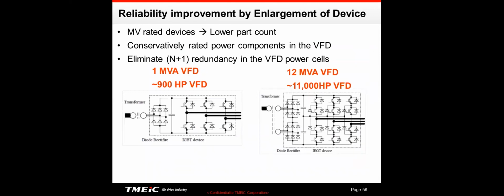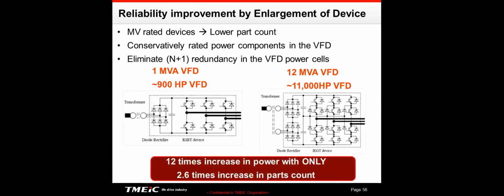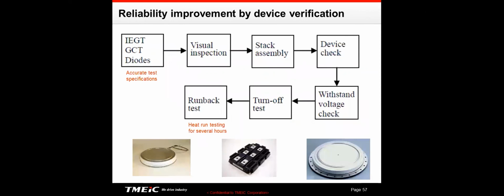Reliability can be improved by reducing the parts count, by being very conservative in your application of the IGBTs and the power devices. TMEIC's opinion is these things are so reliable that some manufacturers will say, oh, we're going to give you extra cells and we'll have N+1 reliability. So if a cell fails, then we can continue operating. If you've got 15, 20 year reliability, generally more components is just generally going to reduce your reliability. And my personal experience with that is that the N+1 generally lowers the reliability rather than increases it.